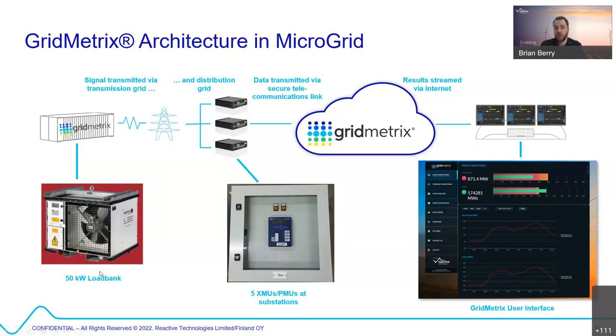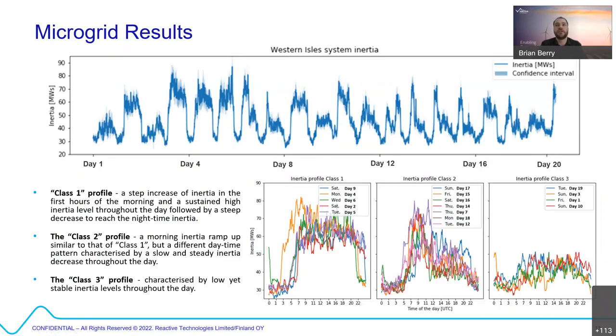In this case, we used a 50 kilowatt load bank, which we ran at 15 kilowatts. You can rent these. This is just a standard load bank that we rented, and we tied it into a solid state switch that we controlled. We had PMUs and frequency measurements all around the grid, five in this particular grid. That goes into our cloud platform where the calculation is and produces inertia. So the end result is, over around 20 days of running, we got a full trend of inertia.